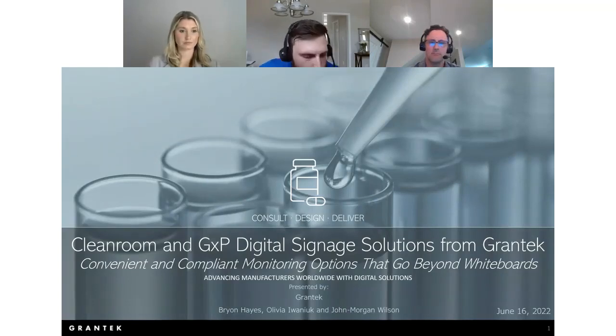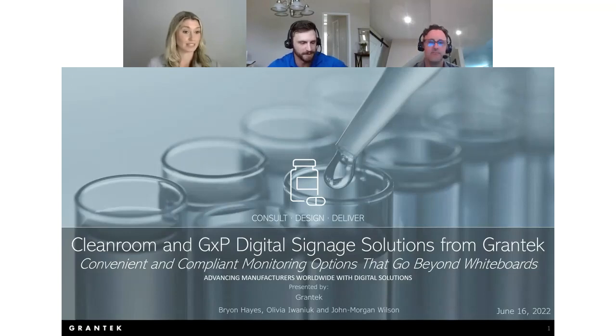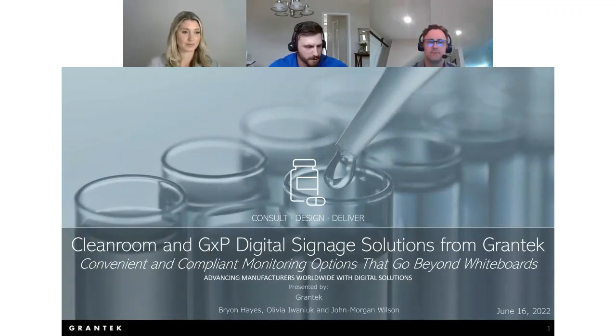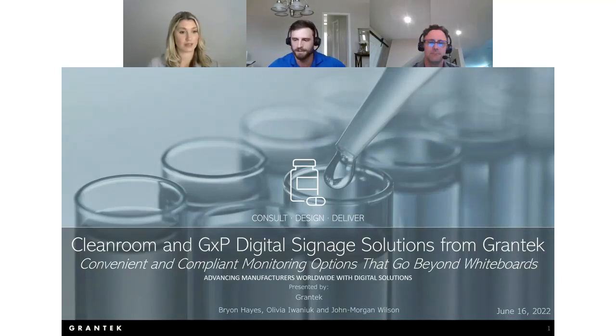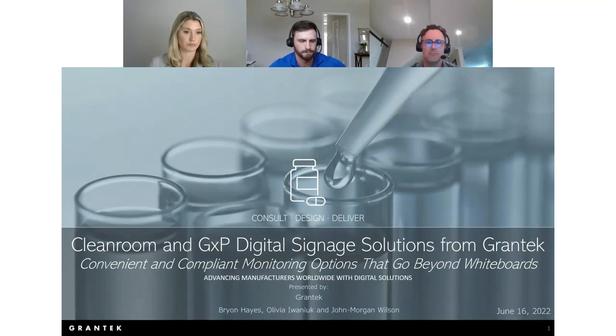Another question regarding in-wall versus on-wall: to reiterate, it is the same display. For on-wall installation it just has stainless steel wrapped around it. Additionally, if the display is the on-wall style, does it also require silicone sealant? Yes — in order for it to be clean room compliant, the on-wall style still requires silicone sealant to ensure there is no room for any unclean air to get through.